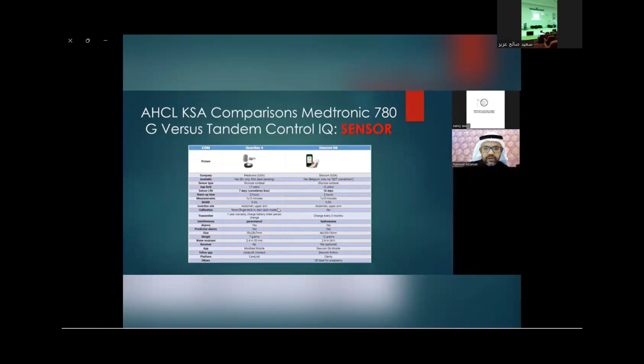So these are the differences in the algorithm. Without going into much detail, the Medtronic 780 has an algorithm targeting a specific target value, based on which it will deliver an auto correction. But in the Tandem, because they are using a different algorithm, they will be targeting the range between 112.5 to 160. Also, Medtronic has the ability of using a temporary target, but Tandem has two different modes called sleep mode and sports mode that can be used.